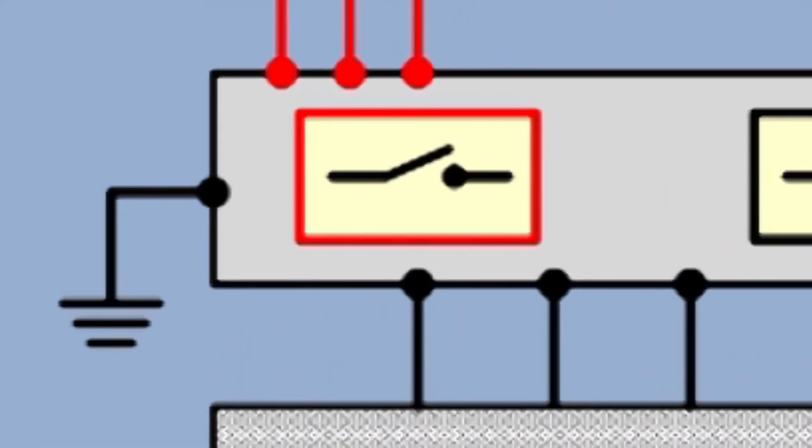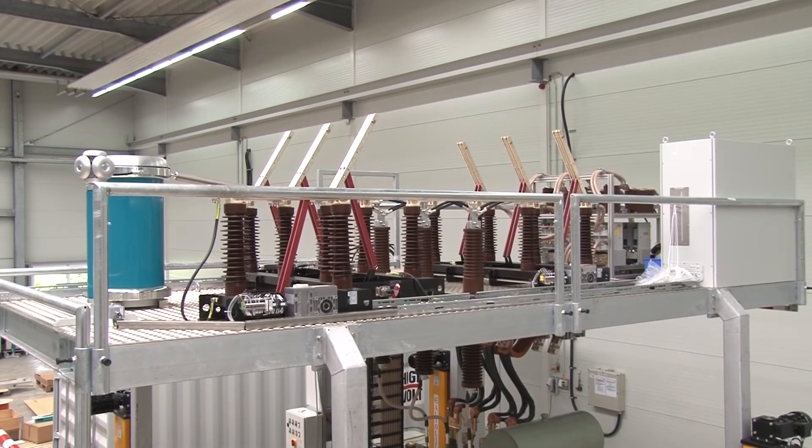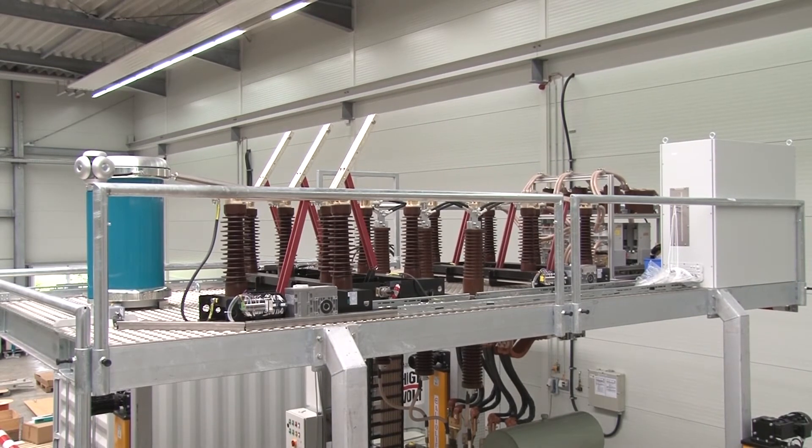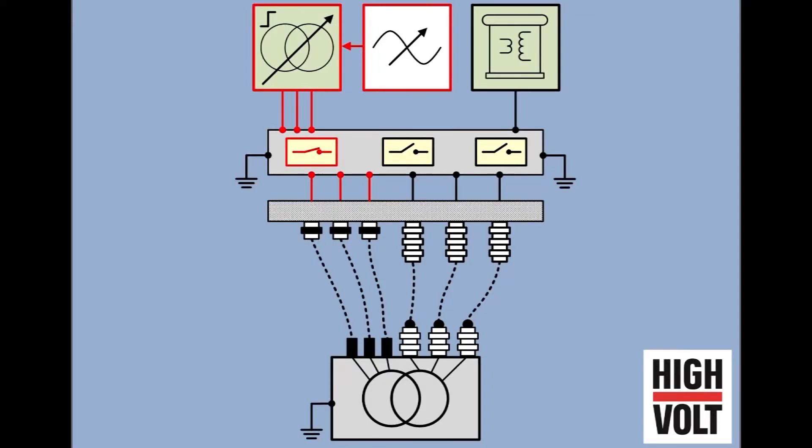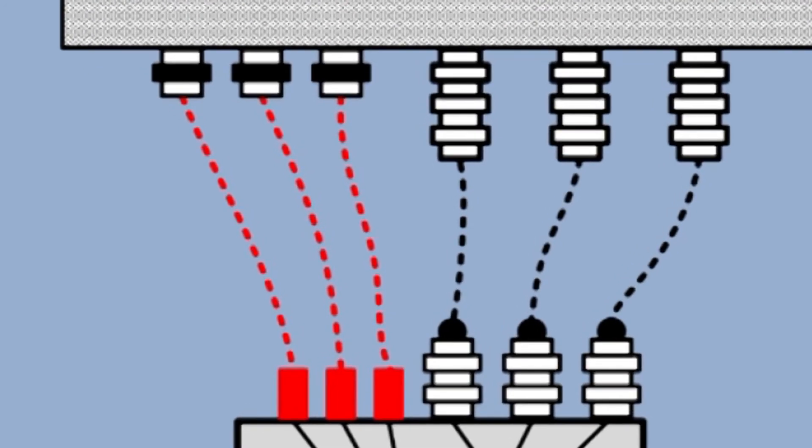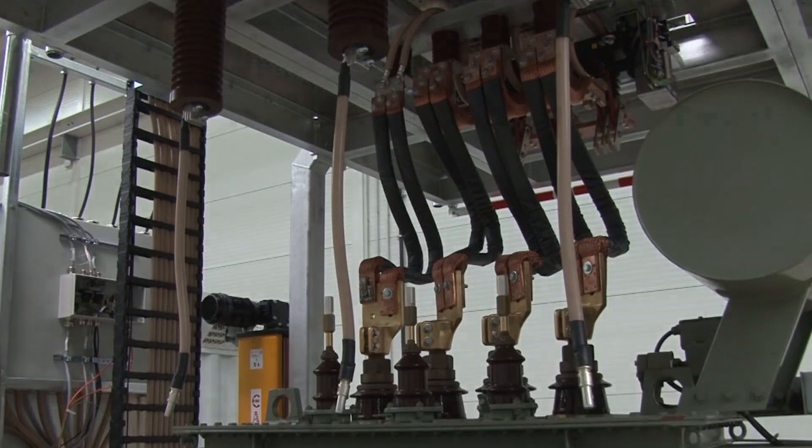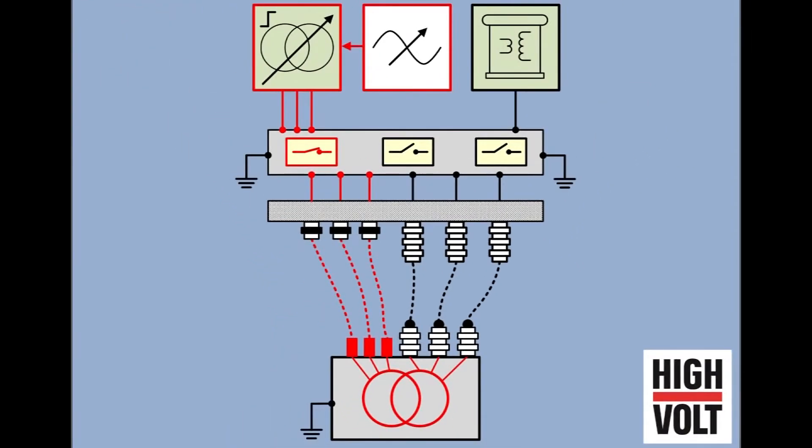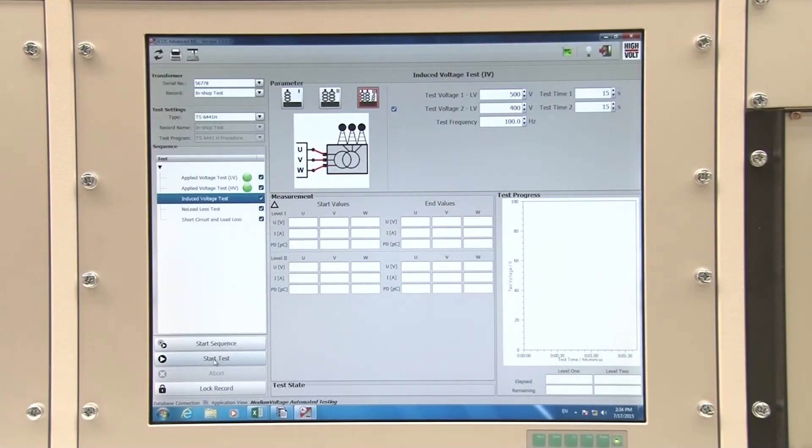There are further automatically controlled disconnectors to provide a safe connection with the low voltage side of the test object. The test voltage on the high voltage side is generated according to the ratio of the transformer under test. The pre-selected test sequence runs fully automatically.